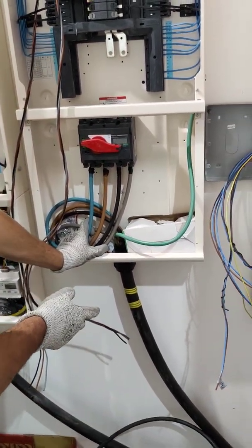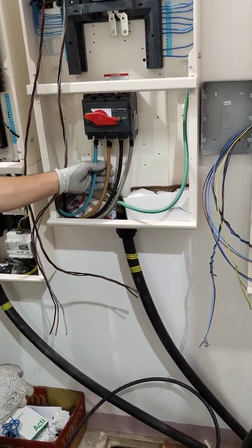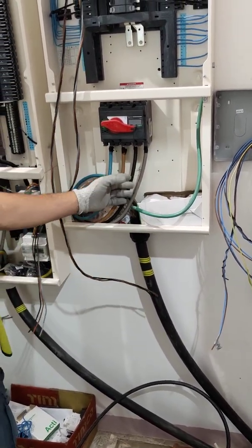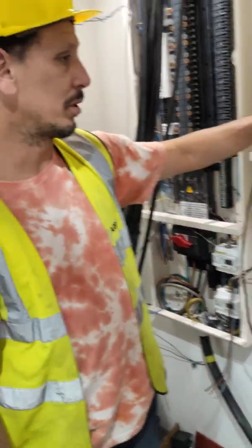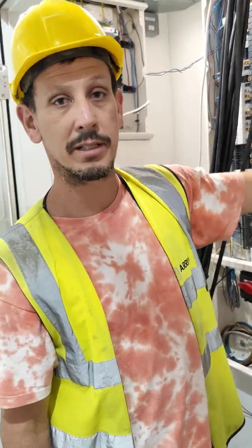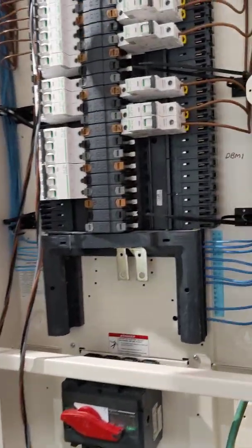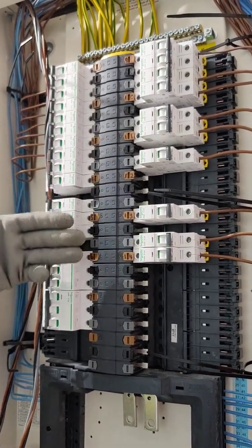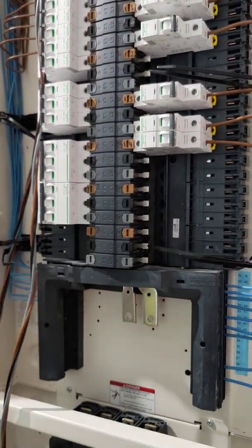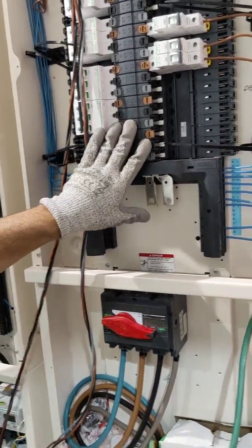To power all this up, we have a main cable coming from outside of the building. In this case, we have a temporary connection from a generator, and it has 3 phases, a neutral and an earth. So that will power this whole board, and it will be connected to the breakers. Behind the breakers we have bar systems that interconnect phase 1, phase 2, phase 3, and this bar system repeats itself throughout each breaker.